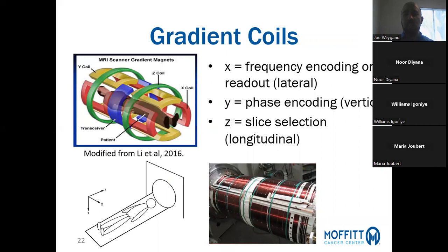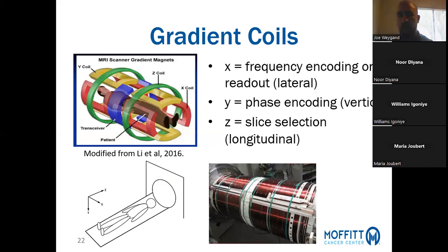The gradient magnetic fields are produced via a set of gradient coils — three of them, one for each principal spatial direction. In MRI, we don't simply call them X, Y, and Z. Our X direction is the frequency encoding or readout direction, associated with the frequency encoding gradient. The Y direction is the phase encoding direction. And the Z direction, which is along the direction of the external magnetic field — so the cranial-caudal axis of the patient — is what we call the slice selection direction, associated with the slice selection gradient.